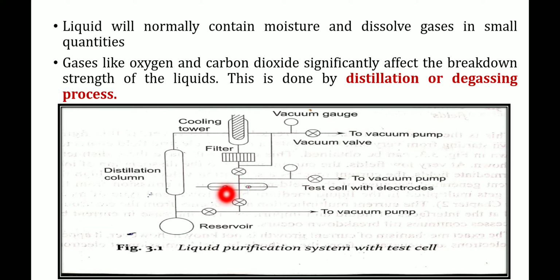So after taking the sample of oil, which test are we going to carry out? We are carrying out the breakdown test, that is, the breakdown strength of the oil is going to be tested here. The breakdown tests are normally conducted using these test cells. For testing pure liquids, test cells are used. In this test cell, a small quantity of oil is taken, and the cell consists of the electrodes used for breakdown voltage measurement.